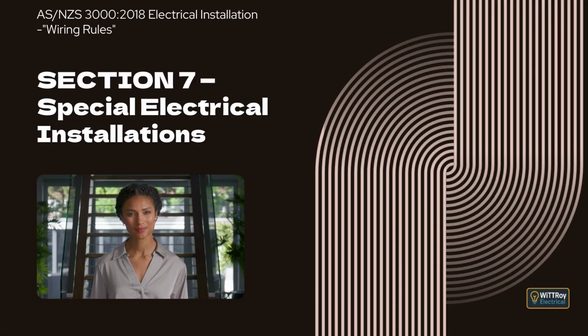Clause 7.9.3.3 Facilities for Mode 3 and Mode 4 charging. This clause explains that higher mode charging systems must comply with requirements for circuit capacity, dedicated final subcircuits, suitable RCD protection, direct connection of equipment, provision of an isolating switch, and minimum installation heights for outlets or cables.